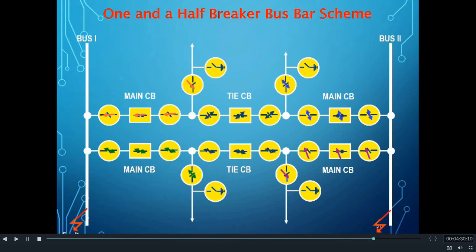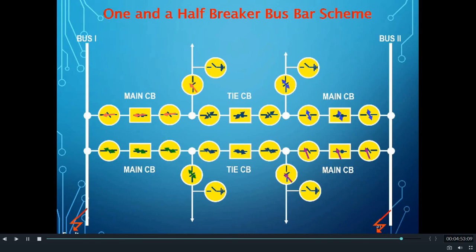If you refer to my earlier videos on the double main cum transfer as well as double main and transfer busbar schemes, a fault in both buses together will obviously interrupt the whole system. Hence, the one and a half breaker scheme is more advantageous over those schemes, but at the cost of one additional circuit breaker for each pair of feeders.